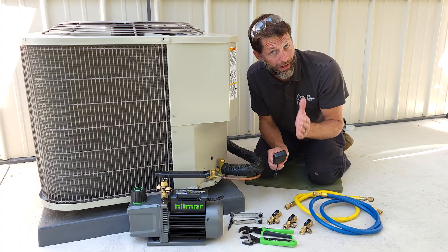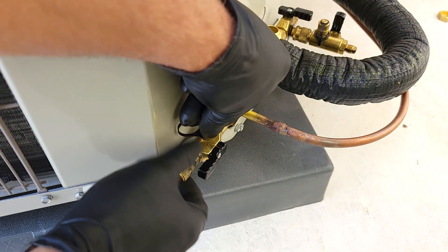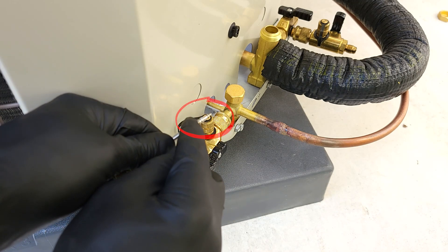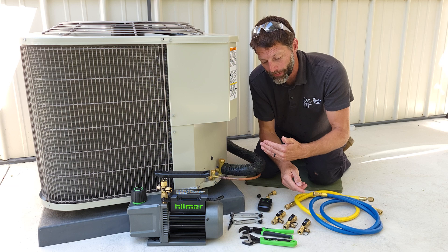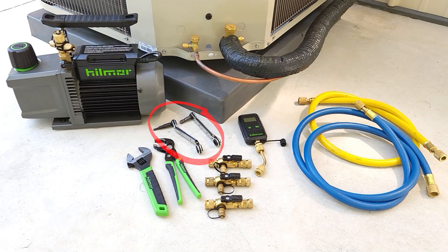We need to get a vacuum below 500 microns. We're going to be using valve core removal tools because these are rated down to 20 microns in order to hold the vacuum. I use three valve core removal tools - I'll show you why in a little bit. I also like to utilize two ratcheting service wrenches, and then we just have our holdback adjustable wrench and pliers.